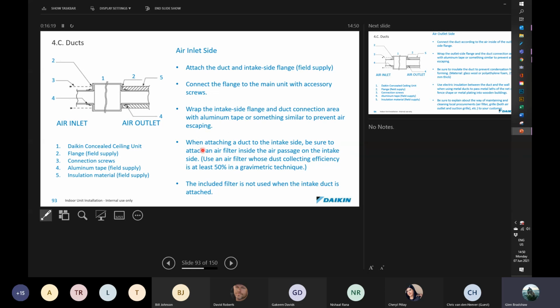When attaching the duct, be sure to attach the air filter inside the air passage. On the intake side, use an air filter whose dust collecting efficiency is at least 50% of the gravimetric technique. An included filter is not used when the intake duct is attached. So if you've got an intake duct, don't install the filter in the back of the unit. If you're going to use the filter, you're either going to put it at the return air grill, or you're going to put your own, maybe an RAG with a return air grill with a filter media already in it. Then you would not need to use the Daikin filter.